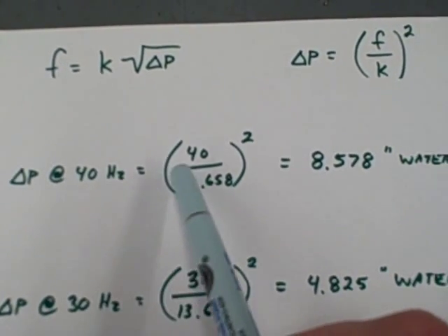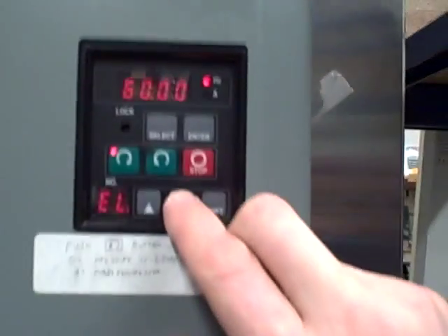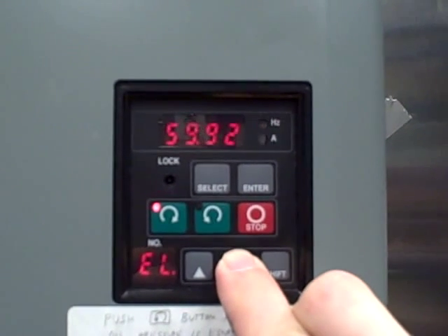So here I've calculated what the differential pressure ought to be at a frequency of 40 hertz instead of 60 hertz. We expect the pressure to go from previous value of 19.3 inches of water down to about 8.578 inches of water. So we'll come over here and we'll decrease the motor frequency from 60 hertz down to 40 hertz.